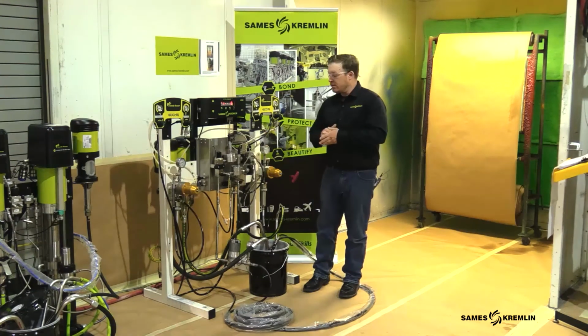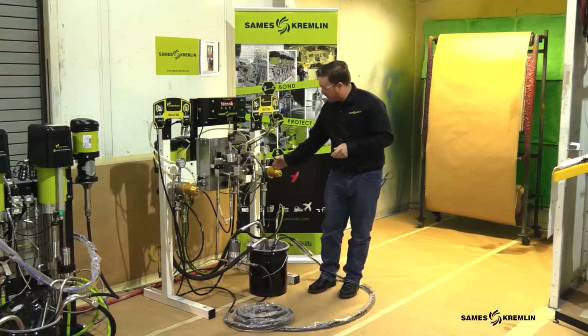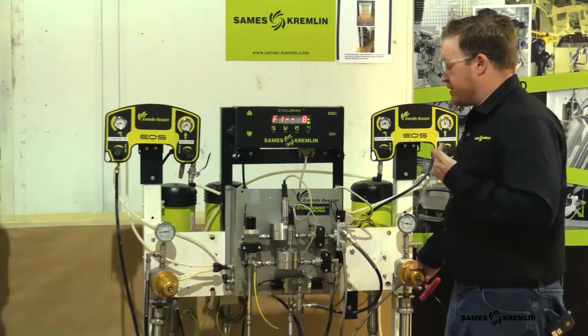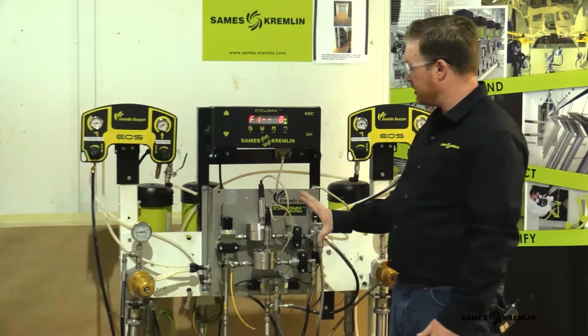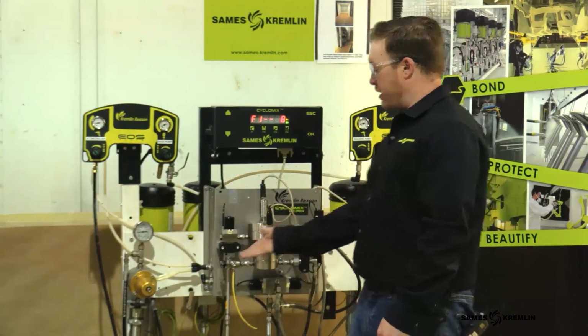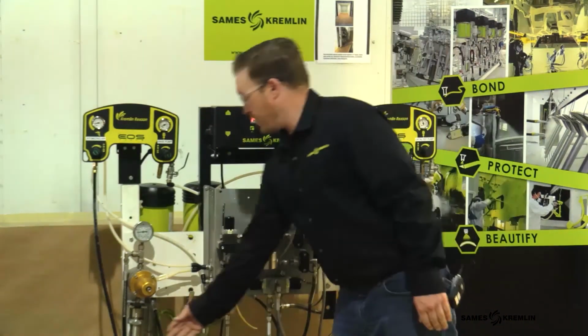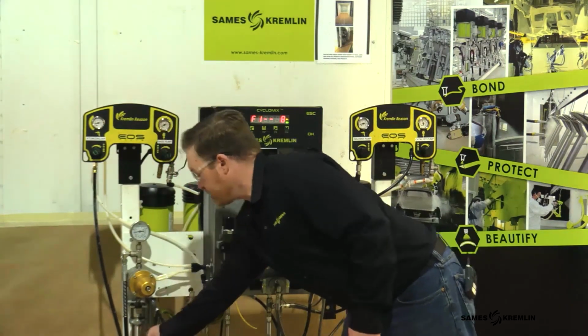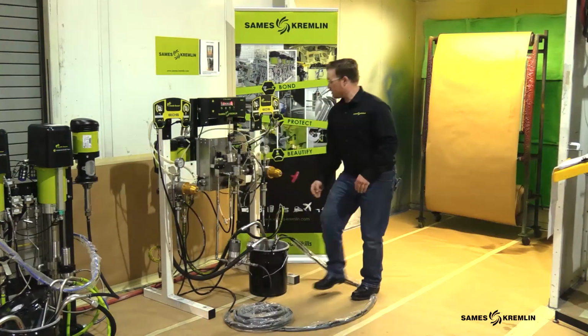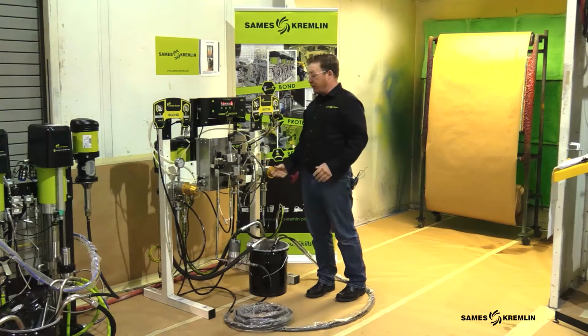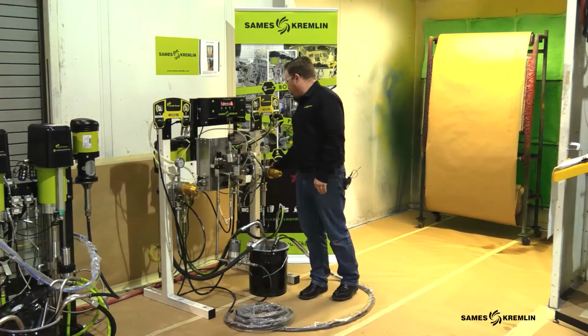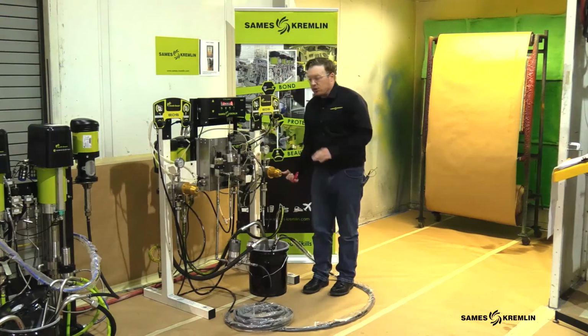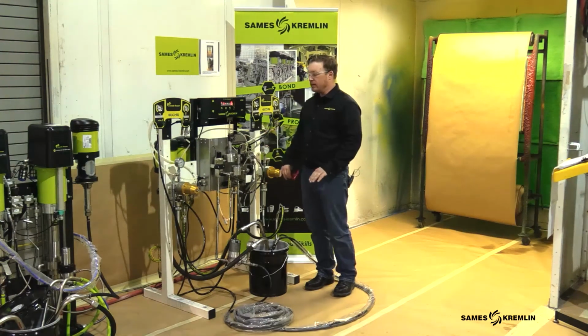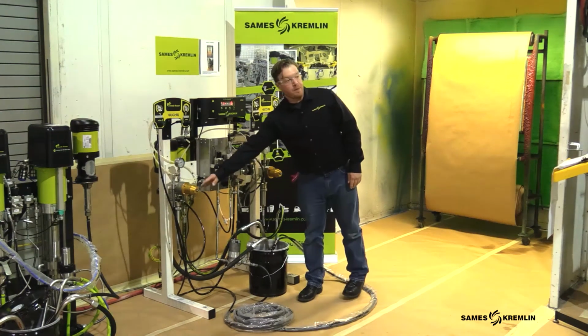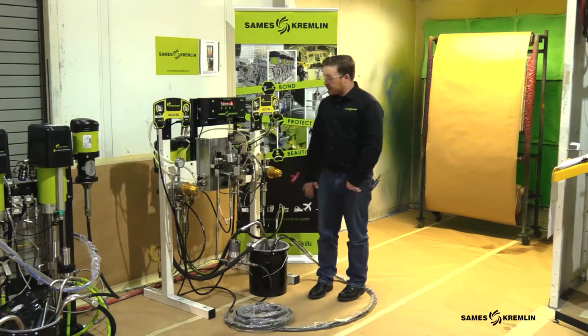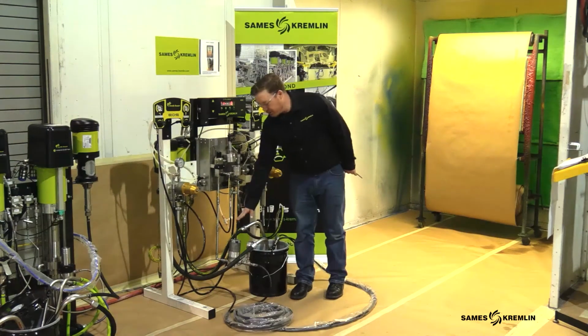The other add-on that I would really recommend is the regulators. You know, the regulators are, in my opinion, a definite requirement to ensure the accuracy and the robustness of the machine. Number one, it comes with a great filtration system. These filters are very economical as far as there's very low volume material in these filters. So they're efficient to clean, efficient to fill and use. And you know, with a lot of these systems, taking shortcuts might look great on paper, but really we've seen the big benefit of having independent supply regulators for each micro. Taking it a step further is going to be an outbound fluid regulator.